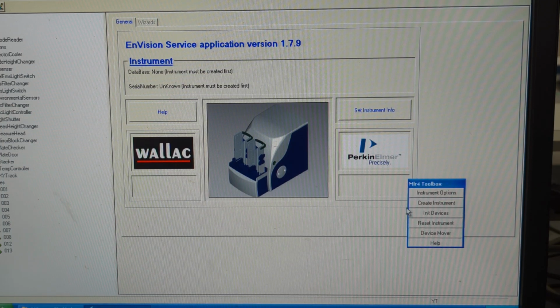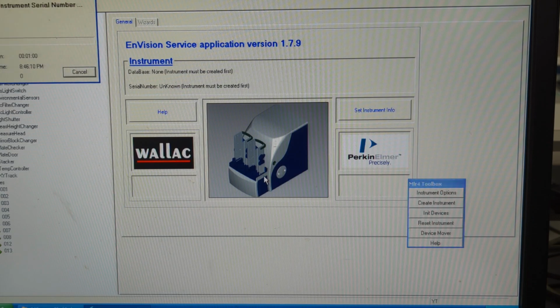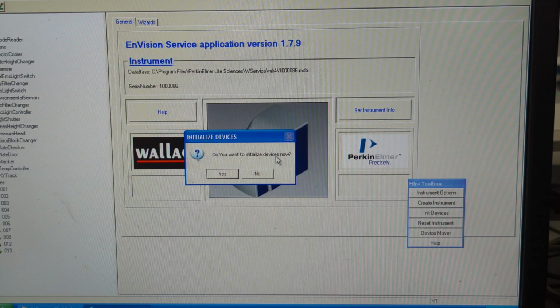But anyway, what we need to do first is create an instrument, and it's just going to read the serial number and get all of the hardware ready for initialization. So it's doing that now, or it's trying to. Sometimes this guy can be a little bit finicky. For some reason on this computer, when you exit out of the actual Envision software that you would use for controlling the instrument in normal operation, and you try to start this guy up, it does cause some problems.